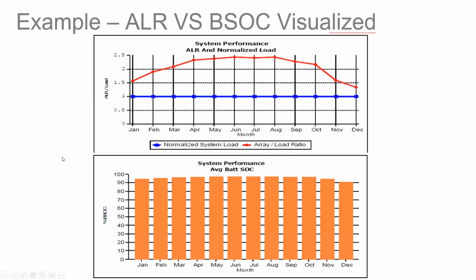So just to recap these two core design parameters, ALR and battery autonomy, visually, you can see on the top, the blue horizontal line is our normalized system load baseline, which is always 1. And then you can see the array to load ratio over the course of the year. December for us in North America is typically our worst solar resource month. And so that's the one that we design around. And that's where you can see the 1.33 ALR. And then on the battery waterfall, you can see on average, we're never dropping below 90% state of charge on average over the course of a month.